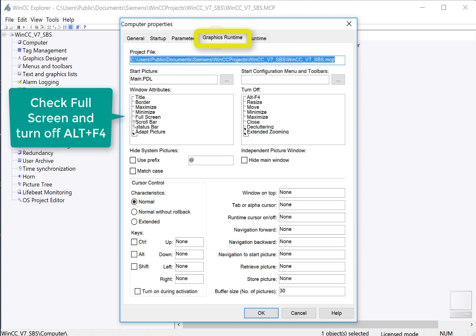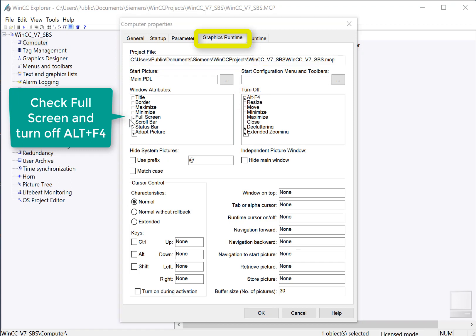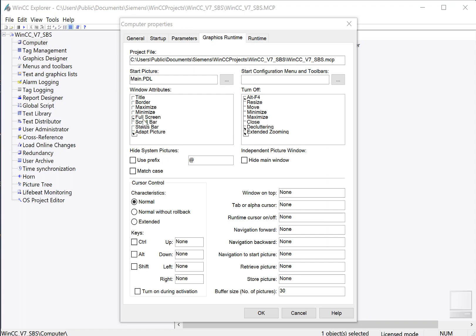On the graphics runtime tab, we're going to check full screen and turn off Alt-F4. Full screen will show the runtime screen maximized without a title bar, and turning off Alt-F4 ensures that you can't use that key combination to close the foreground window. Then we're just going to click OK.